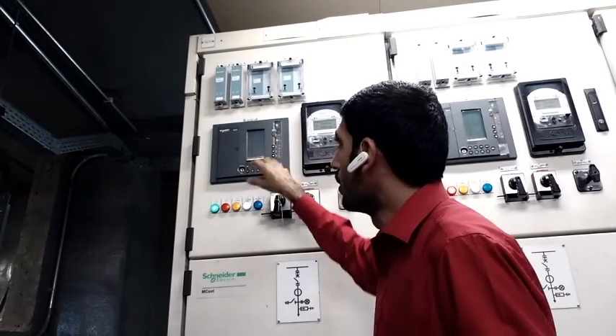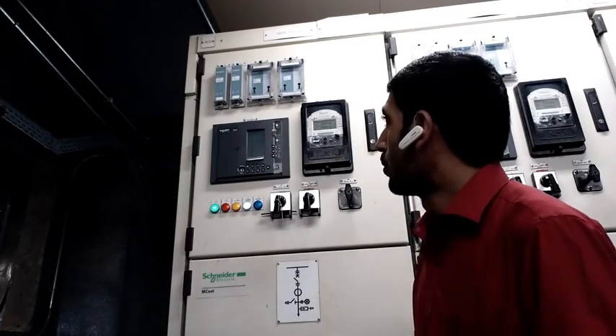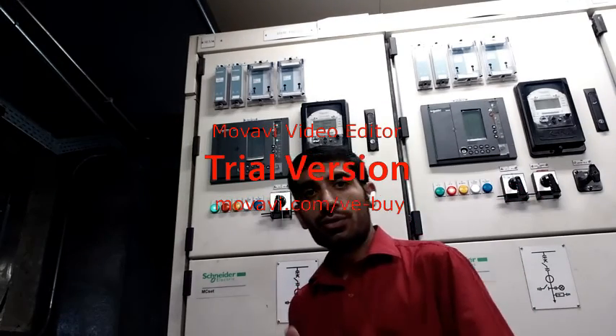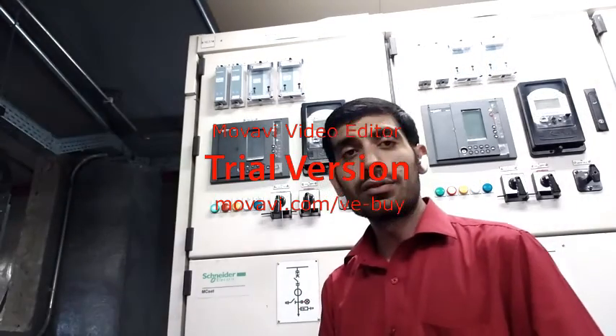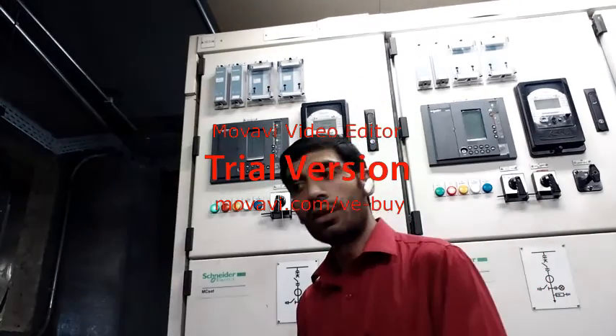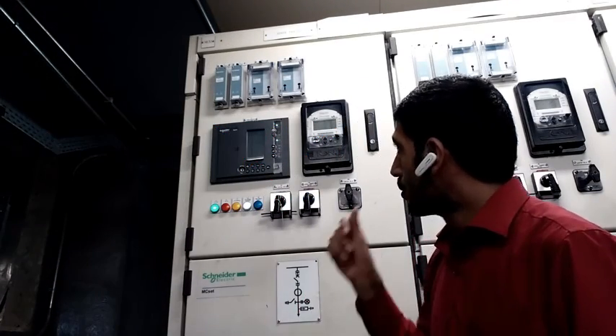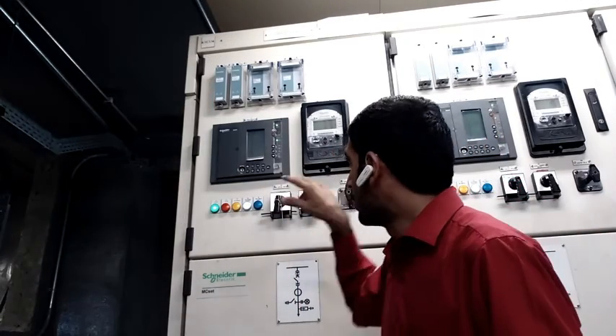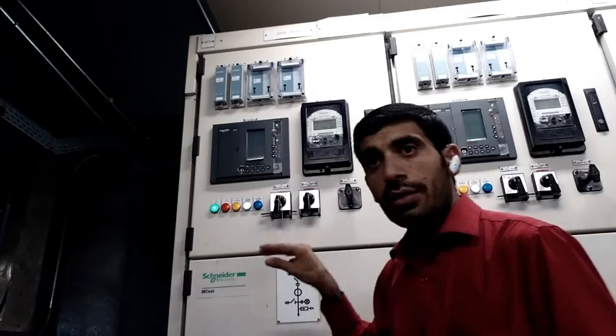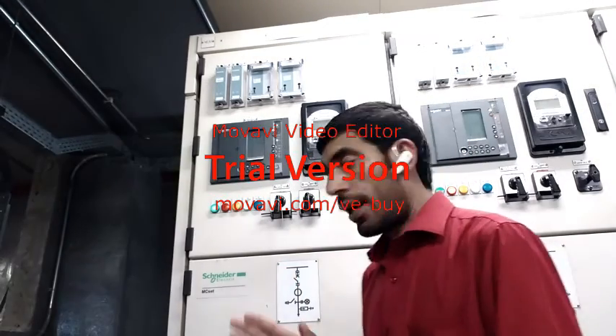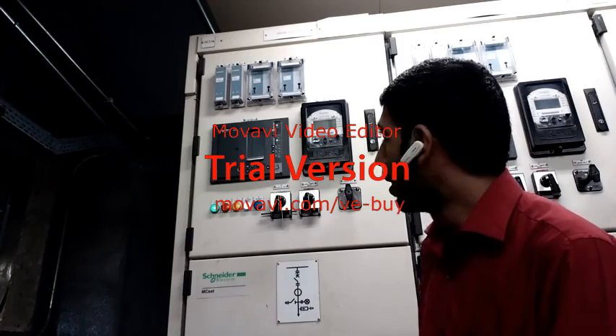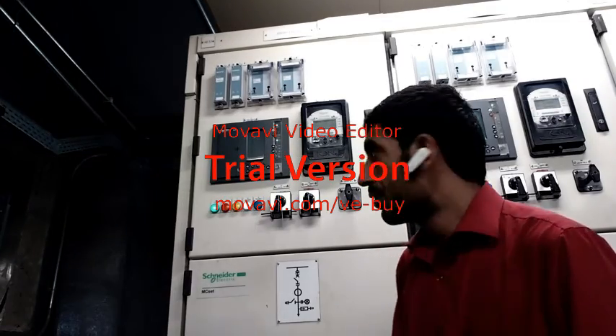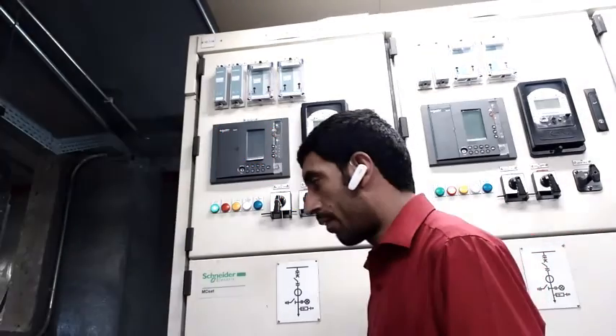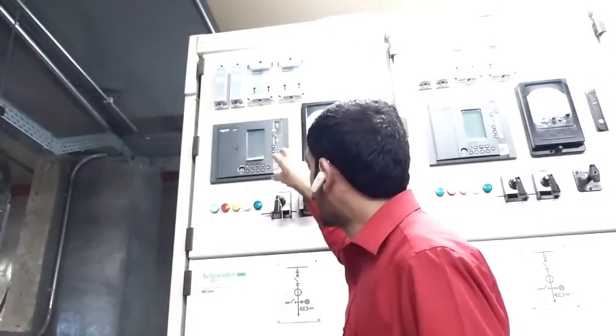We call it Sepam, this one made by Schneider. This is a motor protection relay. We use this relay for different protections: short circuit, earth fault, overcurrent, under voltage and over voltage. We inject 3-phase voltage through the bus metering VT. We inject 3-phase here in this relay, and we also give 3-phase CT values in this relay. And we can see here how much our load is. We can see it here in this relay.